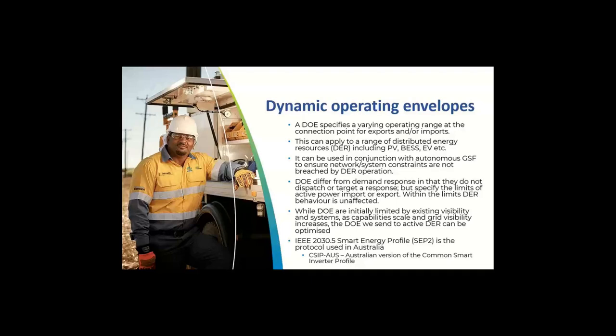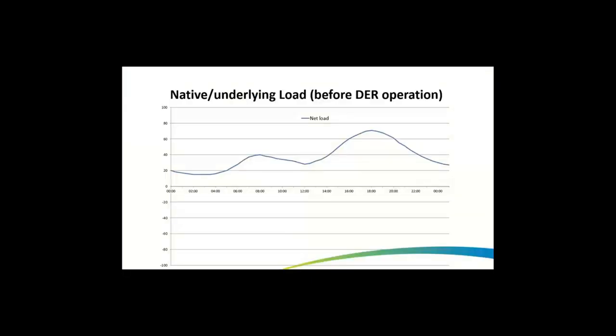In Australia, we use the standard IEEE 2030.5, or Smart Energy Profile, and we have specified CSIP-AUS as an Australian version to specify these dynamic operating envelope requirements. Here's a brief example. Here you can see a traditional load profile of any sort of residential network, with a peak in the evening, a lull in the middle of the day when many people are at work, and a modest peak in the morning when people are getting ready to start their days.